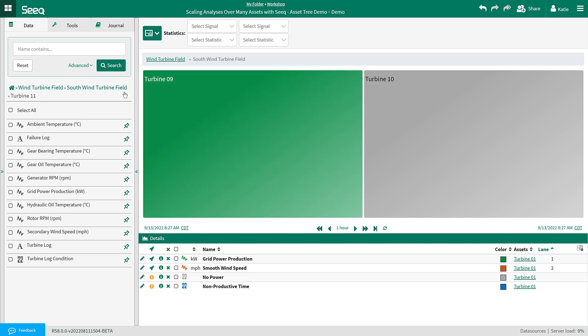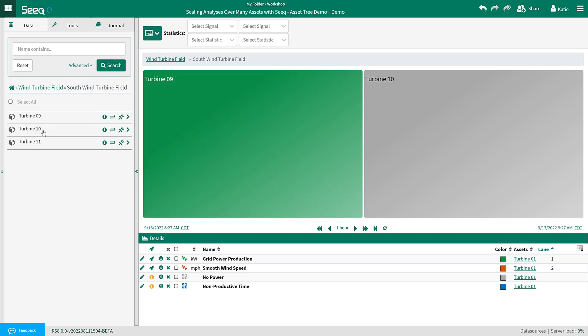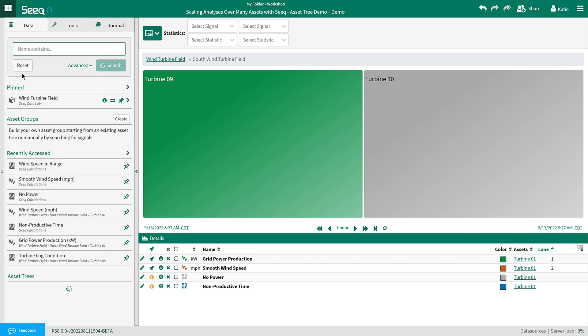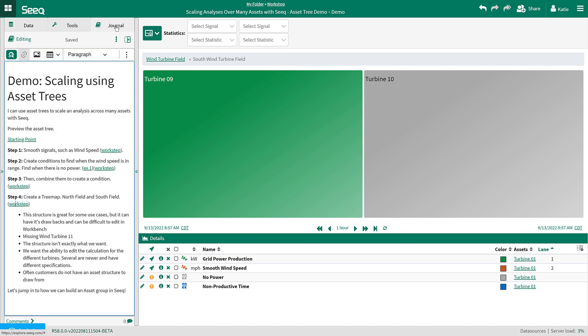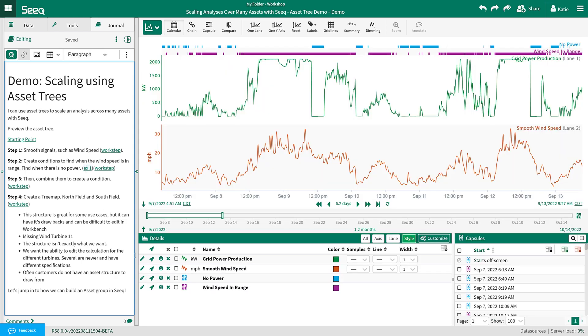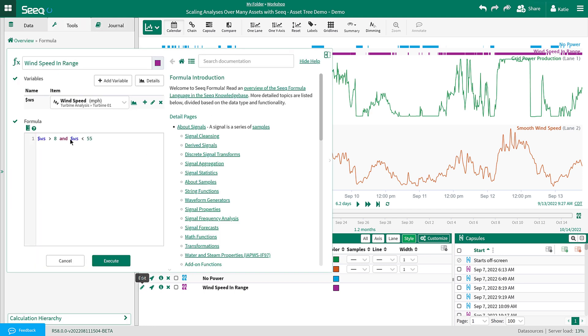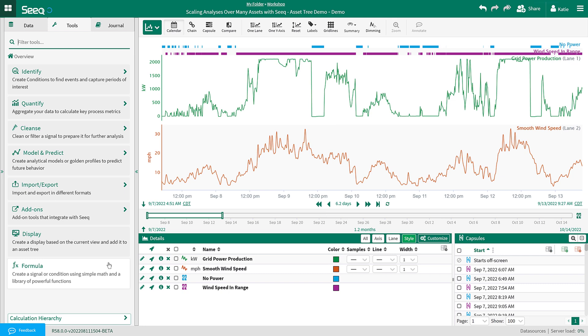Turbine 12 is brand new and hasn't been built into the asset tree. Asset groups allow me to easily map signals to specific assets, edit signals as changes are needed, and add new assets as they come online. Also, in this use case I would like to apply different formulas to the assets. For example, the wind speed range is a little different for some of the wind turbines based on the design of the turbines. Asset groups make it easy to customize formulas for specific assets.